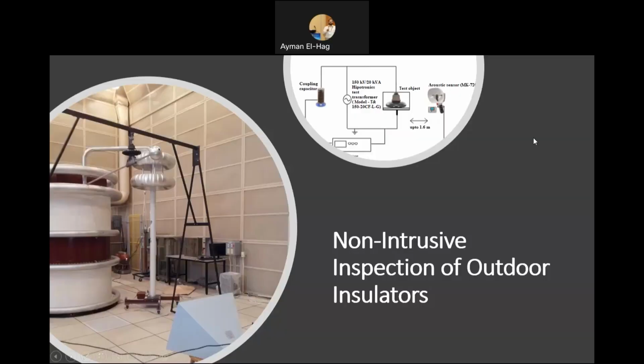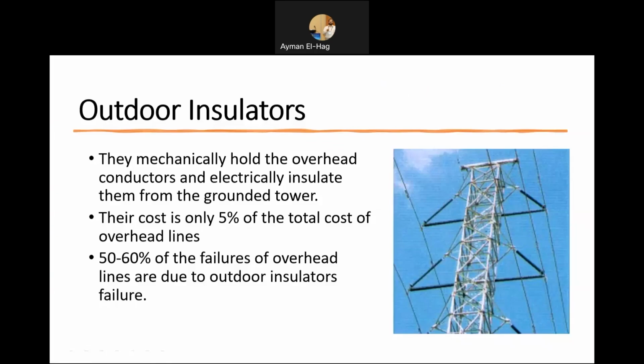Everyone. Today I'd like to talk about something very important related to outdoor insulators, which is the non-intrusive inspection of outdoor insulators. So to start with, as an introduction, outdoor insulators are extremely important to the power system. They mechanically hold the overhead lines, as you can see here, and electrically insulate those conductors which are at high voltage from the tower which is at ground potential.